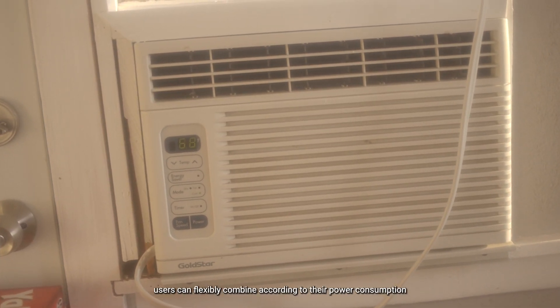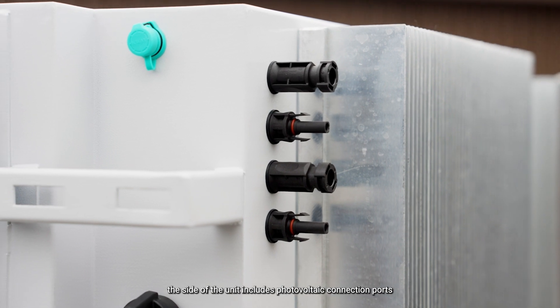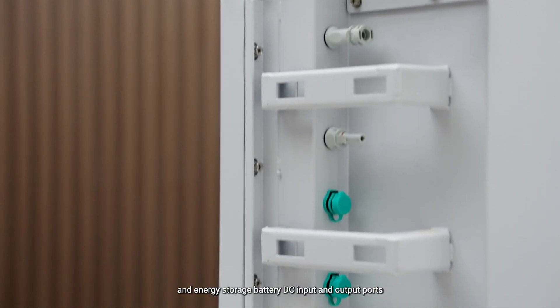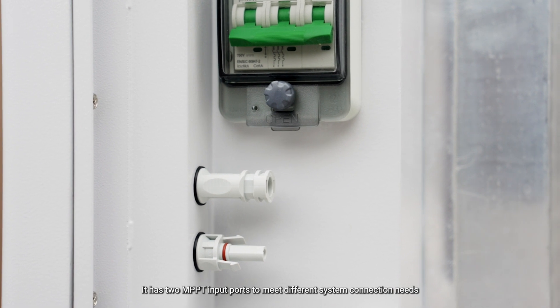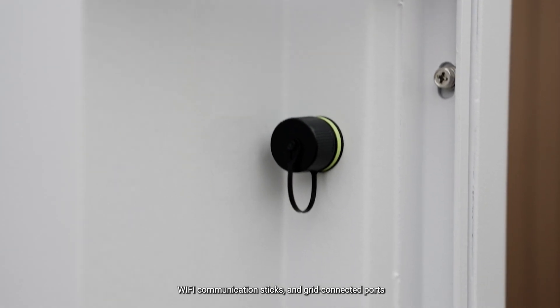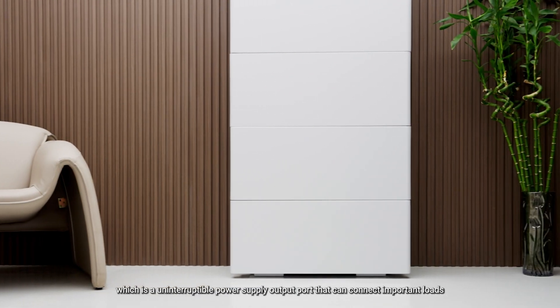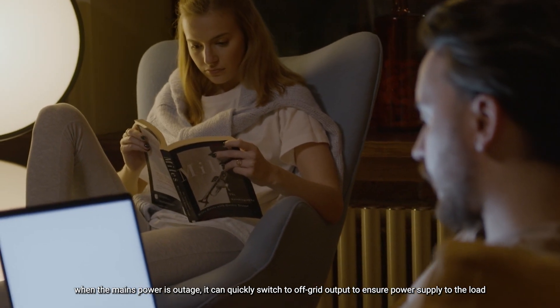Users can flexibly combine according to their power consumption. The side of the unit includes photovoltaic connection ports, BMS communication ports, inverter AC and DC switches, and energy storage battery DC input and output ports. It has two MPPT input ports to meet different system connection needs. On the other side, there are mainly CT interfaces, communication sticks, and grid-connected ports. This part is the EPS port, which is an uninterruptible power supply output port that can connect important loads. When the mains power is out, it can quickly switch to off-grid output to ensure power supply to the load.